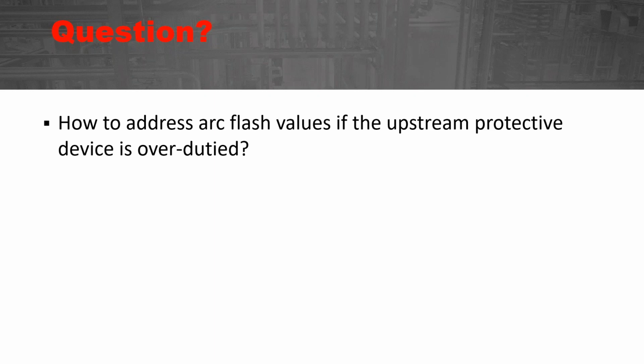There's also these devices called shorting switches, and basically what they do is, if you have an arc flash in a panel when someone's working, it'll detect that and introduce a 3-phase voltage fault in another location on the system that can actually handle the current without over-duty-ing other equipment, and it basically removes the arc flash from in front of a person over to another part in the system that can actually handle the current. And it's just a bolted fault. So there's a number of ways you can, I'd say, protect an over-duty piece of equipment. It's just, what makes most sense for your application and your particular installation.